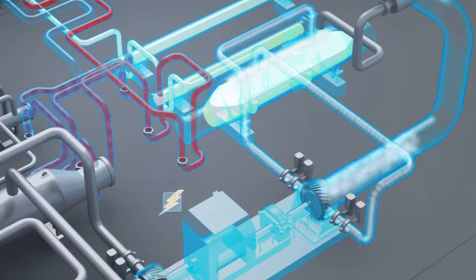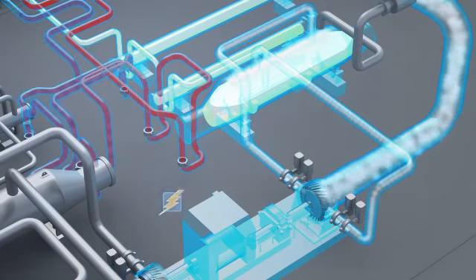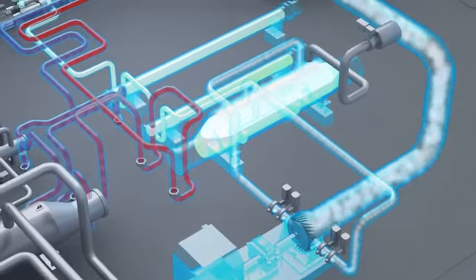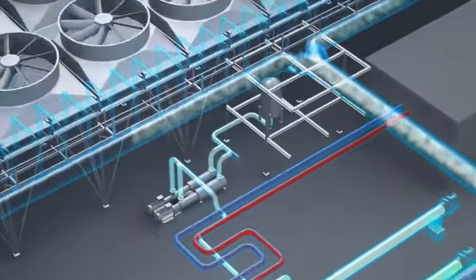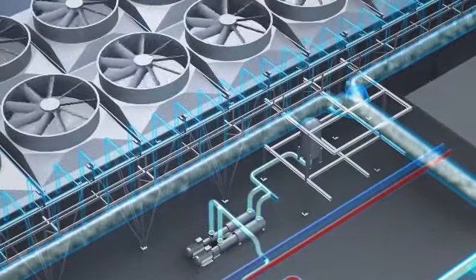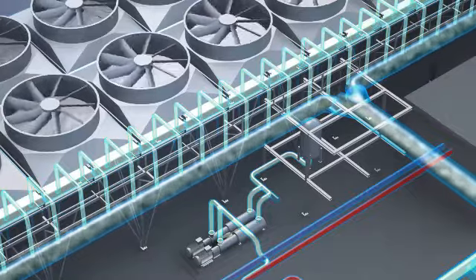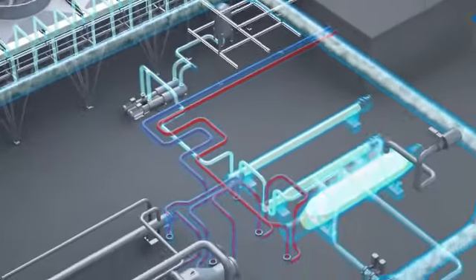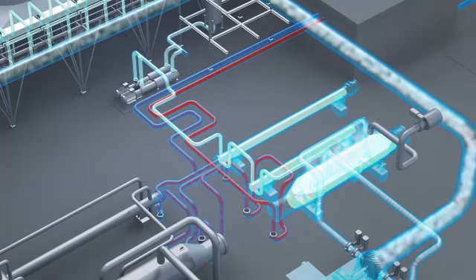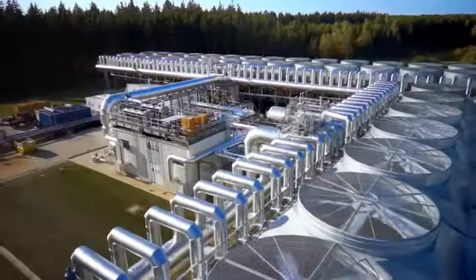The vapor then passes through the air condenser tube bundles, where it is cooled and condensed by the airflow induced by the fans. The organic fluid liquid condensate is finally collected in the hot well and pumped by the ORC pumps to preheater and evaporator, thus completing the sequence of operations in the closed-loop circuit.